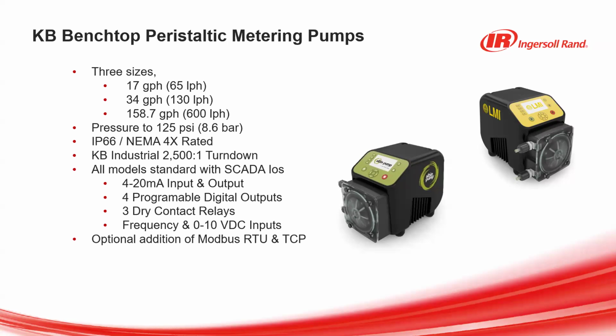And also the tube element is the only element within the pump that's in contact with the process fluid. This makes selection of the pump and setup and commissioning simple, and then ongoing maintenance is not only predictable and can be scheduled in process to increase uptime, reduce the risk of downtime, but also to make the selection of the chemistry for the specific material in the tube simple and easy.